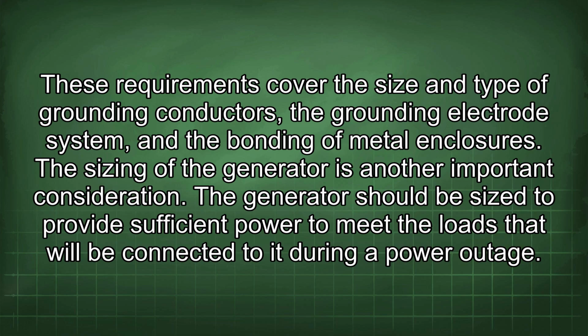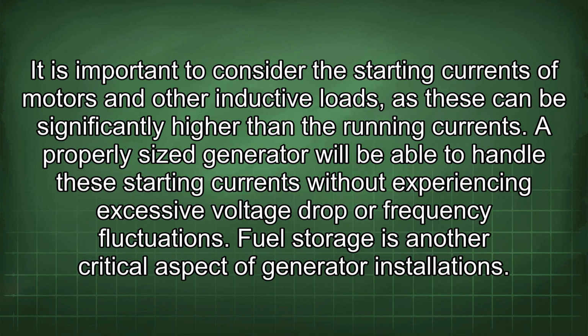The sizing of the generator is another important consideration. The generator should be sized to provide sufficient power to meet the loads that will be connected to it during a power outage. It is important to consider the starting currents of motors and other inductive loads, as these can be significantly higher than the running currents. A properly sized generator will be able to handle these starting currents without experiencing excessive voltage drop or frequency fluctuations.